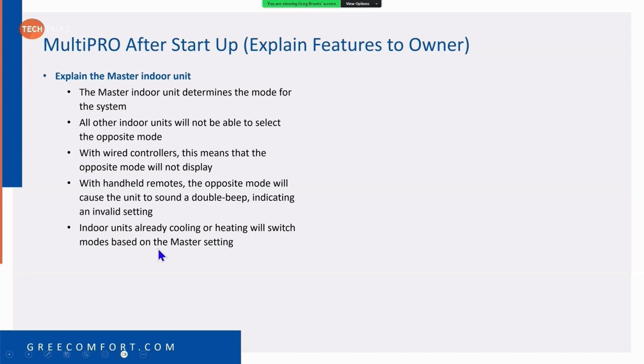Indoor units already cooling or heating will switch modes based on the master setting. That goes back to that loft unit I was telling you about. You've had it in heating season. You've got all of the downstairs units set at 74 degrees in heat. Everybody's happy. You got that loft unit that nobody's up there. You set it at 61 degrees. Then come spring, you got that warm day. You turn the master to cool, and then you go in the first floor and you reset all those to the temperature you want for cooling, and then you completely forget about that loft unit. Now that loft unit's sitting up there holding a 61 degree set point in cooling mode because nobody went up there and changed it. That's what we mean there.